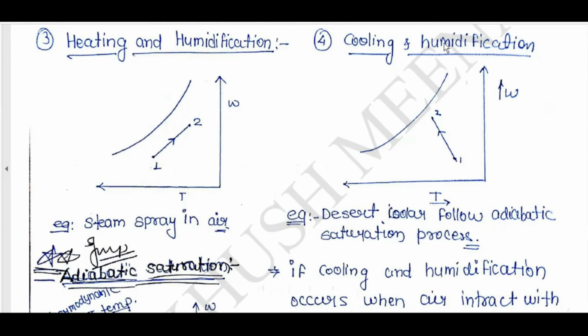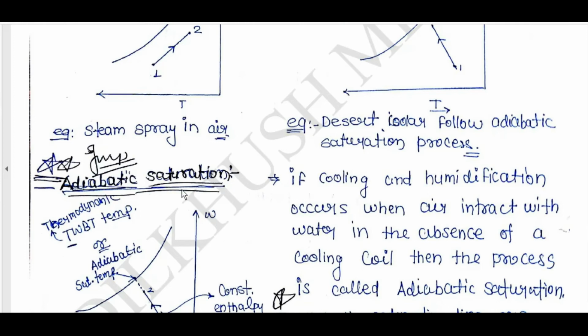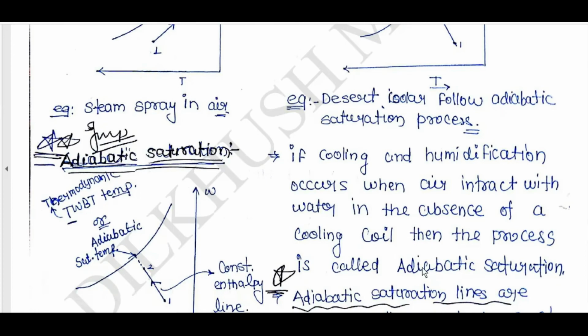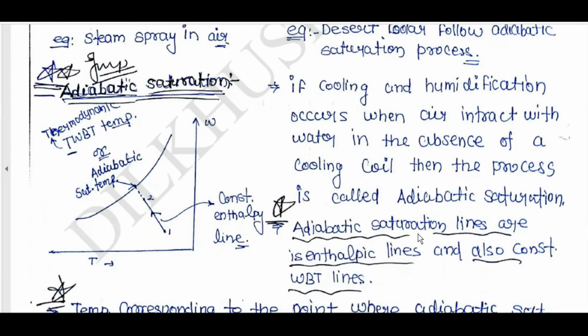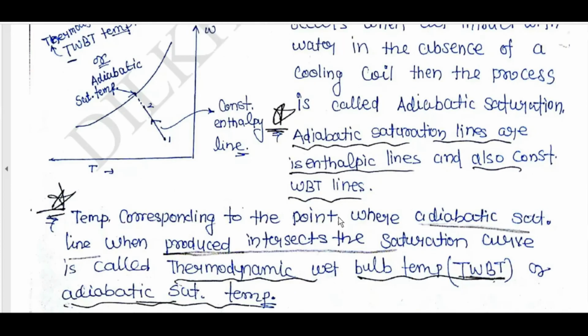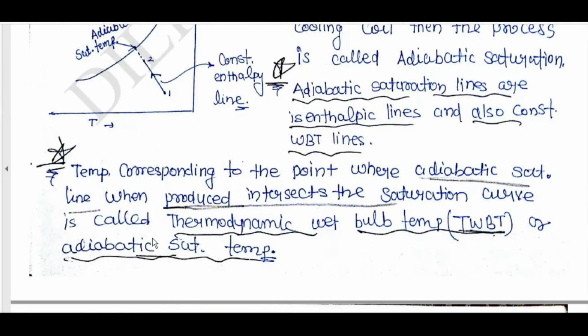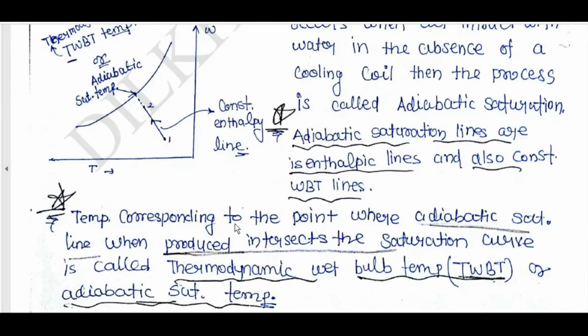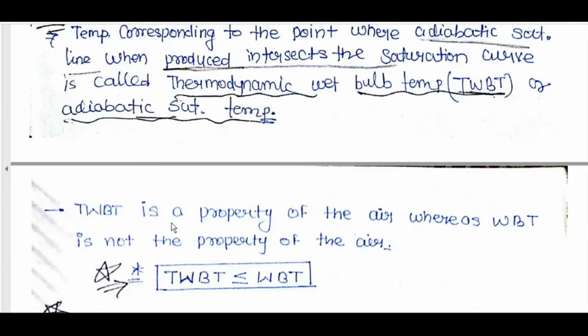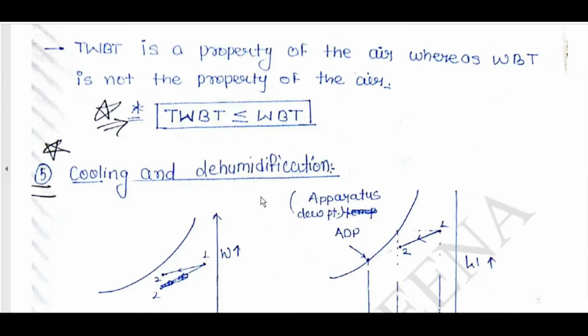Cooling and humidification, for example a desert cooler, follows the adiabatic saturation process. If cooling and humidification occur when air interacts with water in the absence of a cooling coil, the process is called adiabatic saturation. Adiabatic saturation lines are isenthalpic lines and also constant WBT lines. The temperature corresponding to the point where the adiabatic saturation line, when produced, intersects the saturation curve is called the thermodynamic wet bulb temperature or adiabatic saturation temperature. Thermodynamic wet bulb temperature is a property of air, whereas WBT is not a property of air. TWBT is less than or equal to WBT.